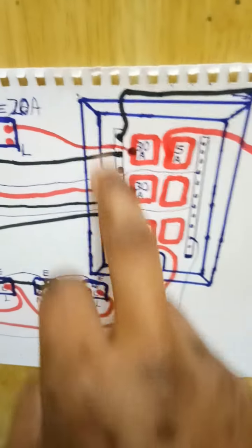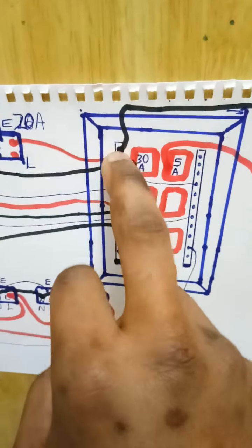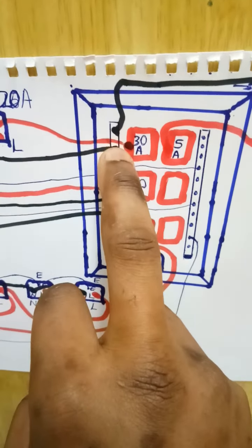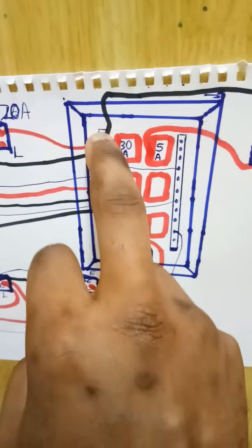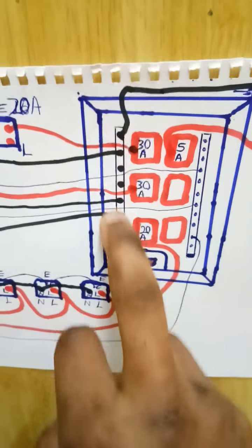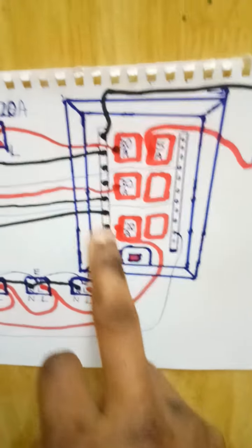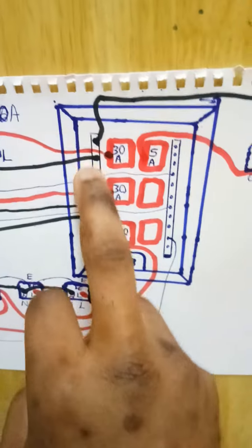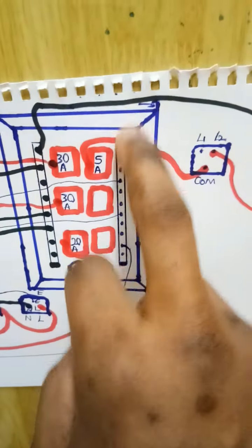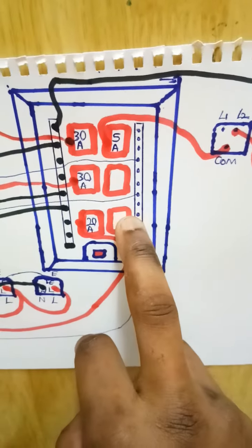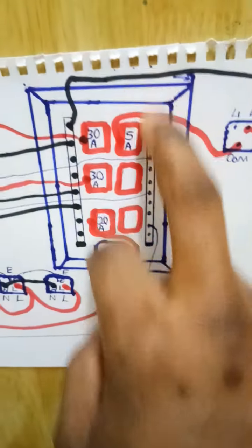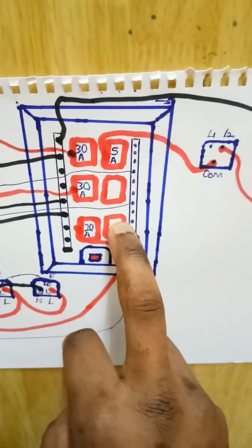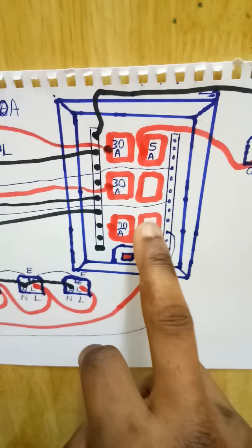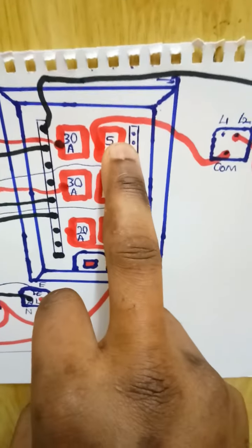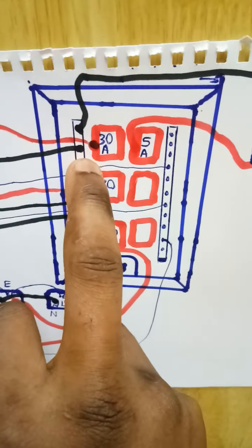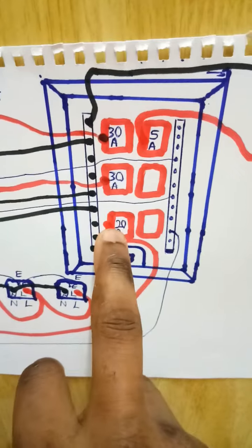Then to find out if it's iron, you can also use a magnet. Sometimes when you place a magnet on this rail, it will be magnetized. That shows that it is iron, not copper, because copper cannot be magnetized. This is a long iron rail to connect all the neutrals, and this one is a long copper rail to connect all the earth wires. These red boxes represent the circuit breakers. As you can see, this is 5 amps, this is 30 amps, this is 30 amps, this is 20 amps.